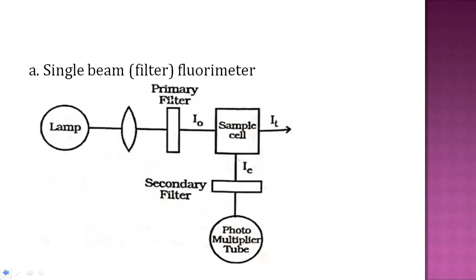These single beam instruments are simple in construction, cheaper and easy to operate, and the range of application can be widened by using different combinations of primary and secondary filters. But the disadvantages are that with these single beam fluorimeters it is not possible to use sample and reference solution at a time because it is single beam, and rapid scanning is also not possible. It means rapid scanning to get the excitation or emission spectrum of the compound is not possible. So these are the basic disadvantages of this type of instrument.